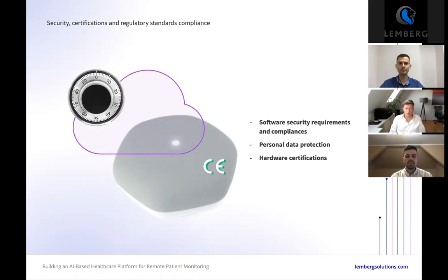fall into? Sure. So, I'm going to oversimplify this just for the sake of time and the point of your question. Medical devices are categorized based on the risk to injure or kill a patient, to be blunt. And so class 3 is the most severe risk class, where you're talking about surgical items, equipment in an intensive care unit, things like that, down to what's called a class 1 device, which has a possible risk to a patient, but not an imminent risk if that technology or that device fails. We, under the current MD regulations in the EU, fall under class 1.